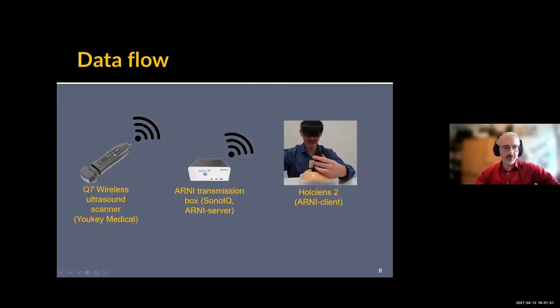The data flow is as follows: the Q7 probe sends the ultrasound images as a live stream wirelessly through our ARNI transmission box. On the box runs the SonoQ software, which is the one from Youkey Medical that you usually have on a tablet or smartphone device. The ARNI server sends the data wirelessly to the HoloLens 2 with the ARNI client, and then you have the exact view that you had before with the standard ultrasound device.